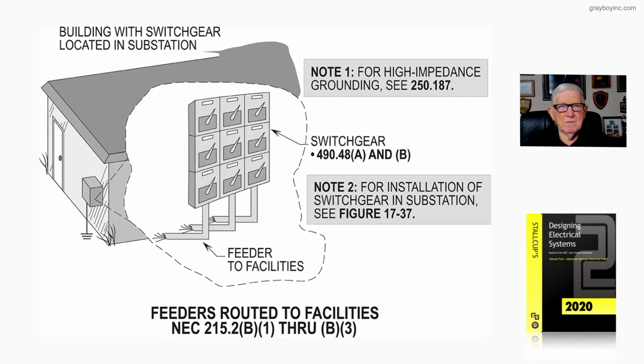17-37. But this figure 17-38, that switchgear you see is located within a building, and the building is located within the substation. And our service point is at this switchgear in accordance with Article 100 when you define service point.